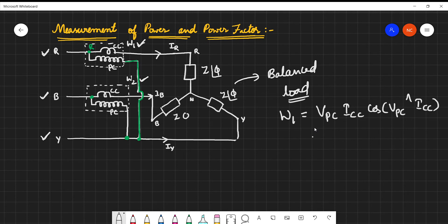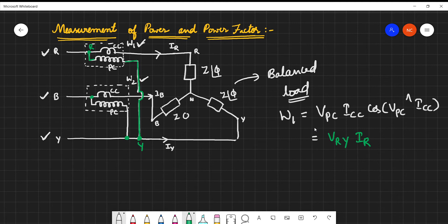Now let us see where the pressure coil is connected. For W1, the pressure coil's first terminal is connected to R and the second terminal to Y, so the voltage across it is VRY. The current through the current coil is IR, and we use the angle between VRY and IR.